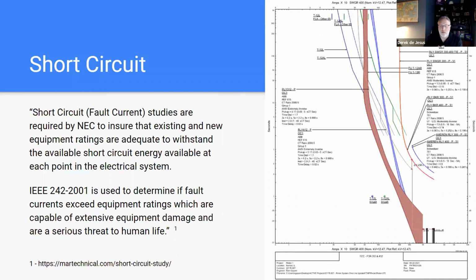One thing that we also mention when we're in the field or in a project, and actually we just ran into this today, is incremental energizations, right? Perhaps a contractor just wants to energize an incoming line switch that feeds a transformer, feeds a breaker, but they're not going to close in on that breaker right away. You should still have a SCCAF study and a SCCAF report available for you and for the team to review, even if they are going to do incremental energizations.